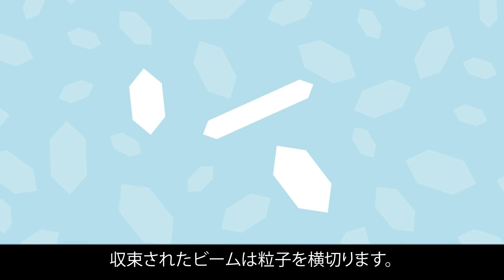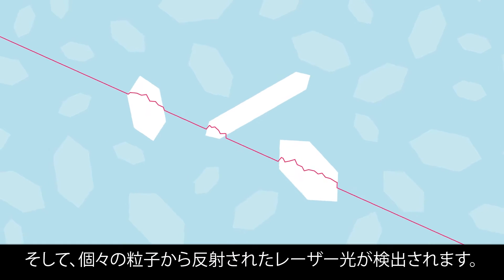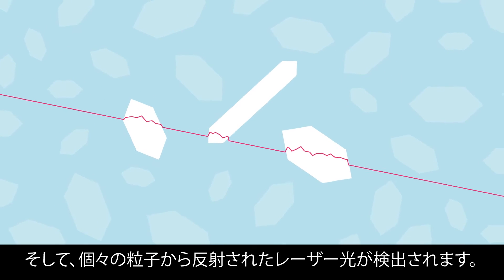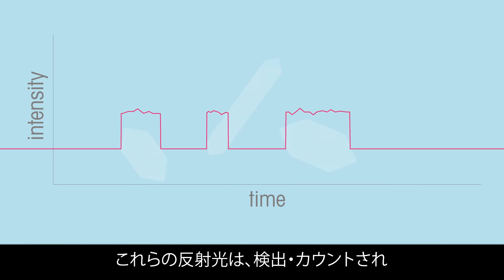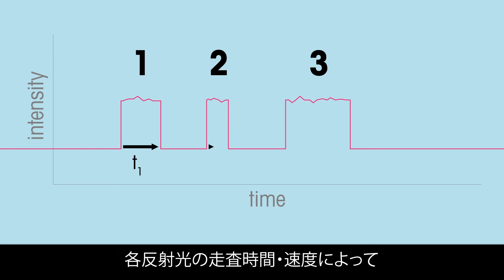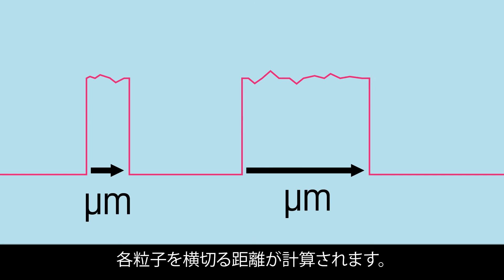As the focused beam scans across the particle system, individual particles or particle structures will backscatter the laser light to the detector. These distinct pulses of backscattered light are detected, counted, and the duration of each pulse is multiplied by the scan speed to calculate the distance across each particle.